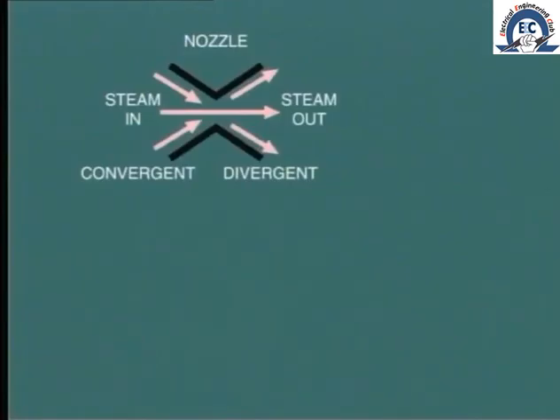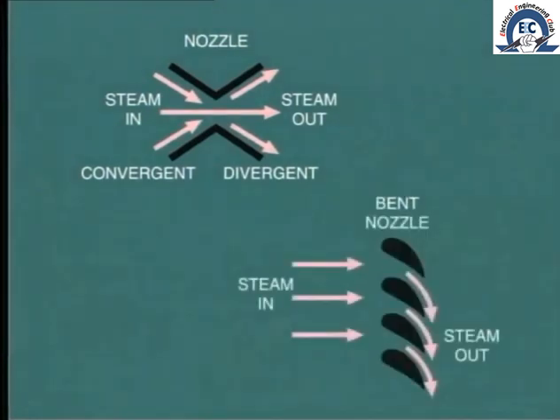Each pair of stationary blades is shaped to form a convergent-divergent nozzle. However, the form of the nozzle is bent to receive the steam exiting from the previous moving stage and then to turn and redirect the steam onto the next moving stage.